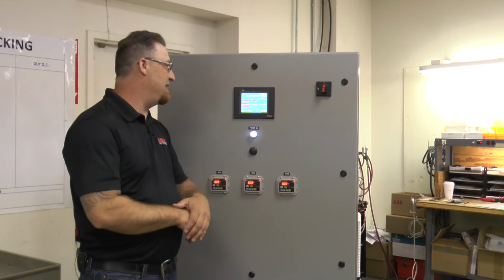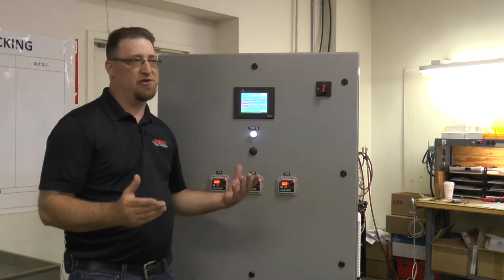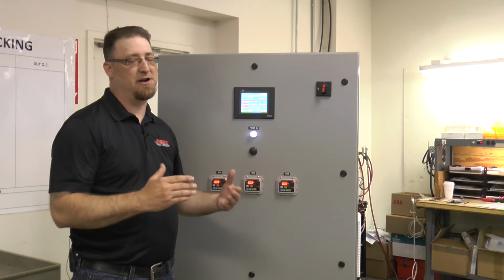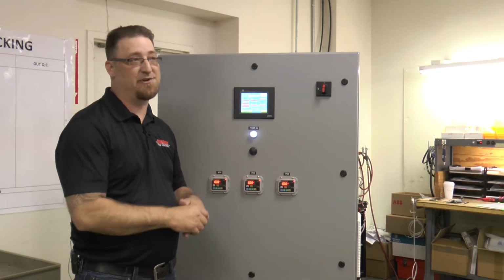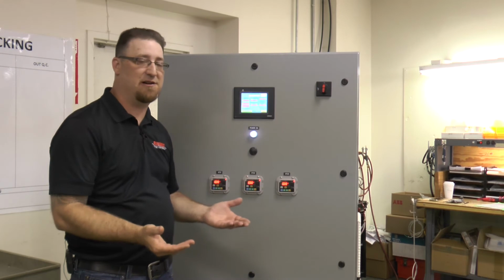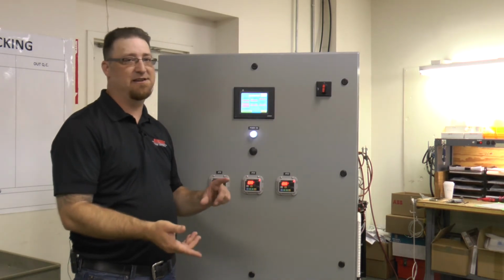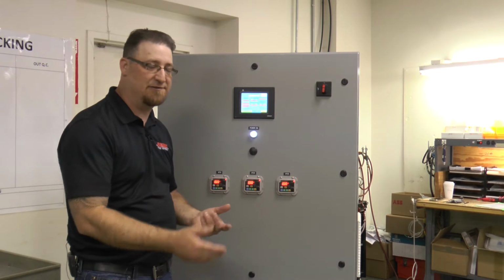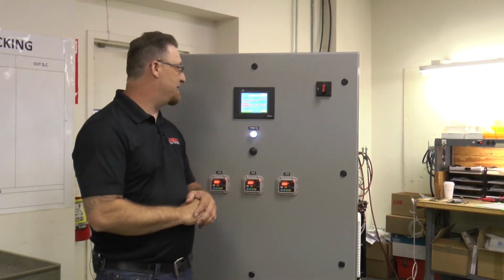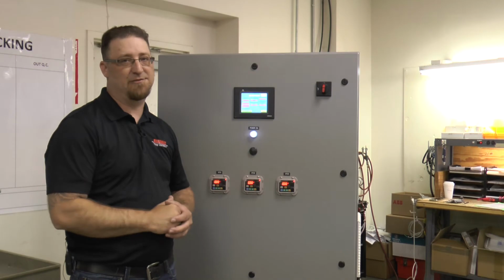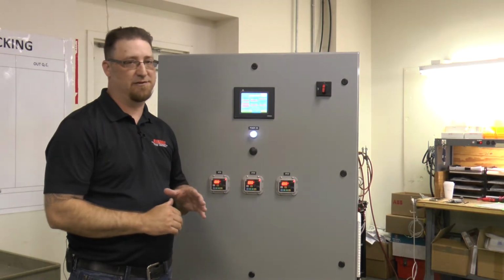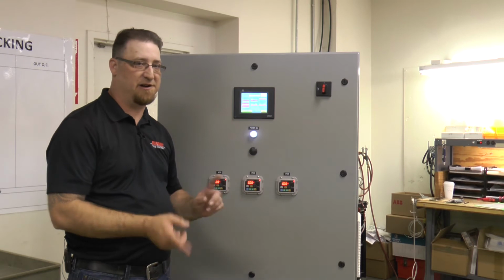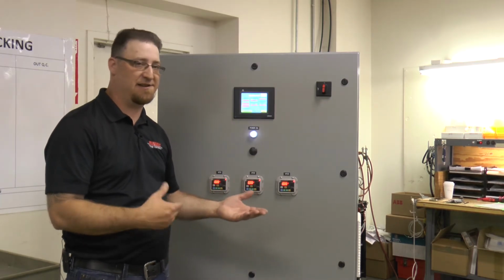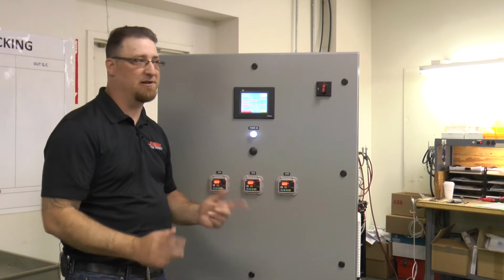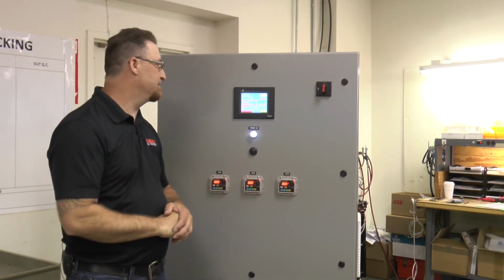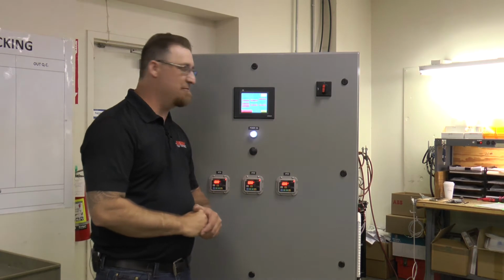And then our switch lead pump screen, that is, do you want that pump to run or to alternate every 24 hours? So when the system is called for more pressure, do you want the same pump to run for 24 hours and then after 24 hours the next pump take over? That's what the 24-hour alternate button is for. In auto alternate mode, every time the system is called on, it will switch pumps. So pump 1 will come on this time, next time it'll be pump 2, and it'll alternate every time that the system comes on.